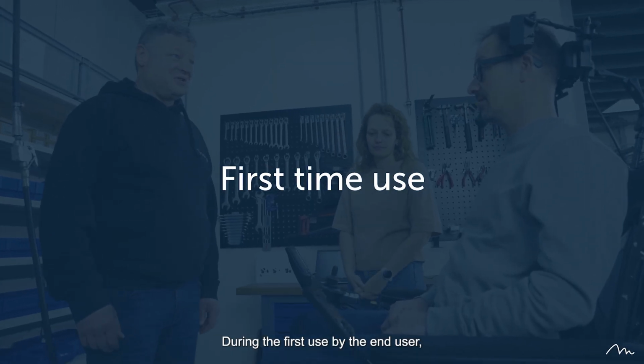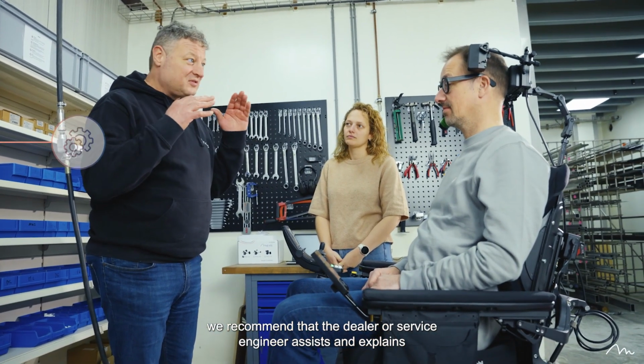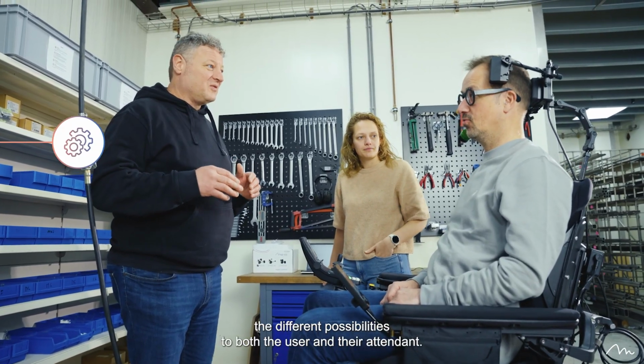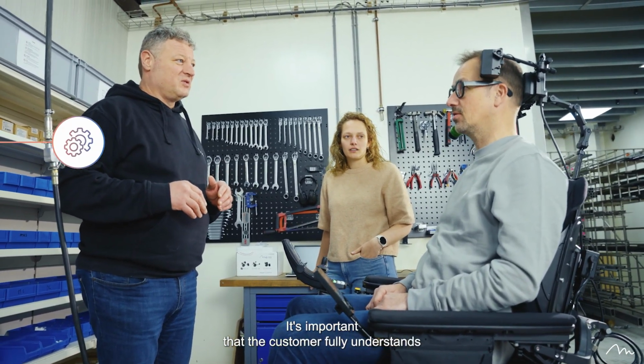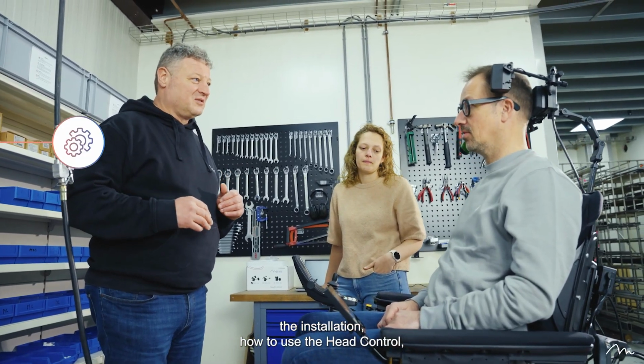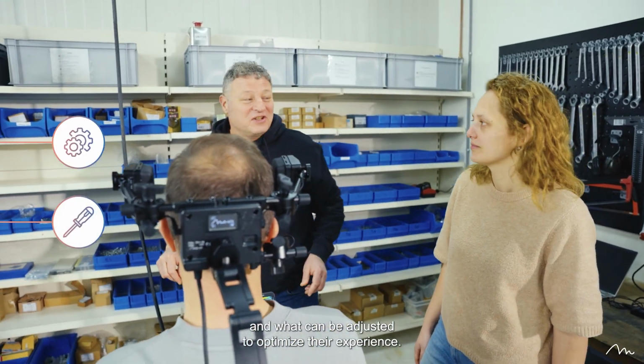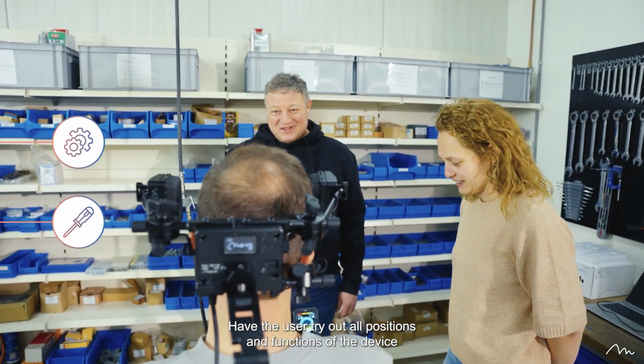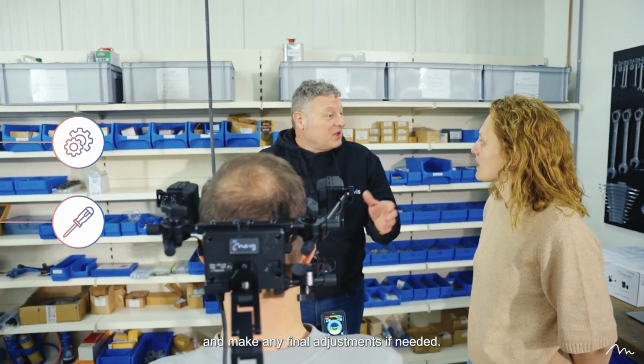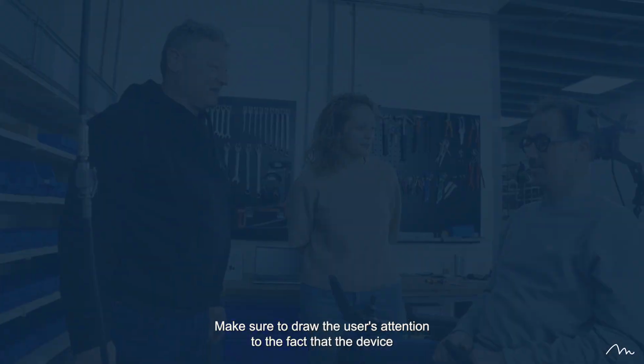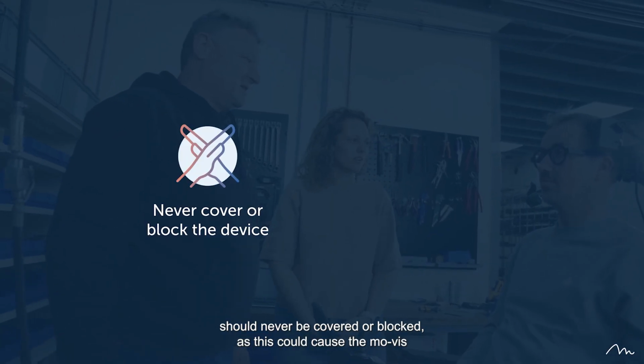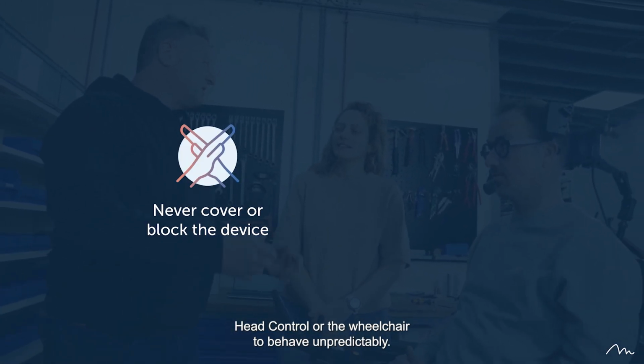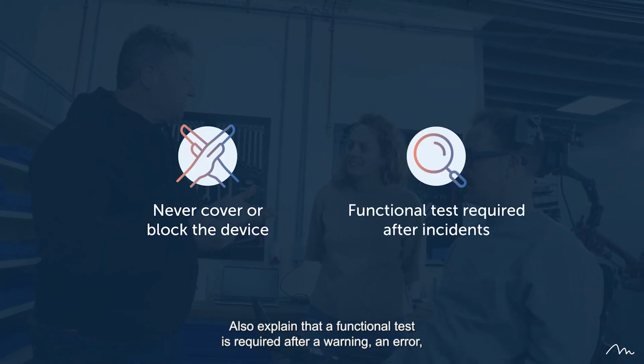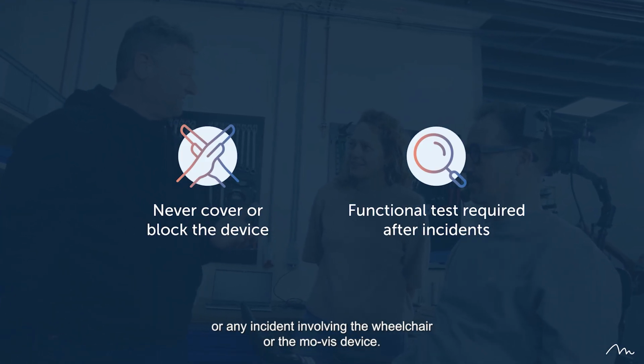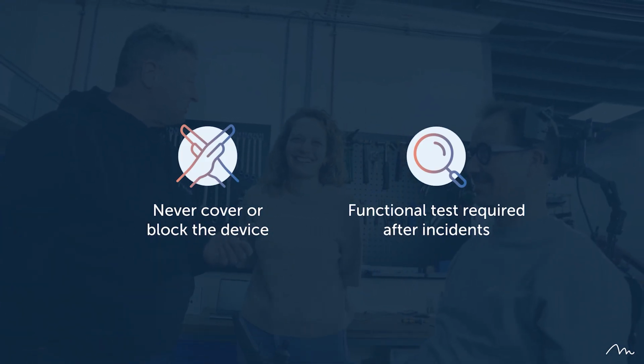During the first use by the end user, we recommend that the dealer or service engineer assists and explains the different possibilities to both the user and their attendant. It's important that the customer fully understands the installation, how to use the head control, and what can be adjusted to optimize their experience. Have the user try out all positions and functions of the device and make any final adjustments if needed. Make sure to draw the user's attention to the fact that the device should never be covered or blocked, as this could cause the mo-vis head control or the wheelchair to behave unpredictably. Also explain that a functional test is required after a warning, an error, or any incident involving the wheelchair or the mo-vis device.